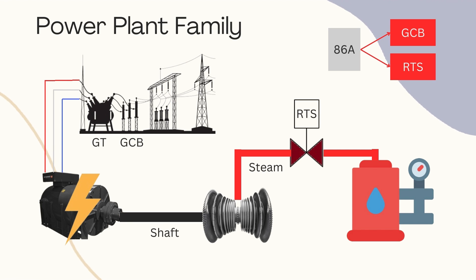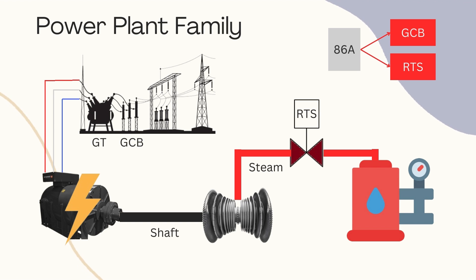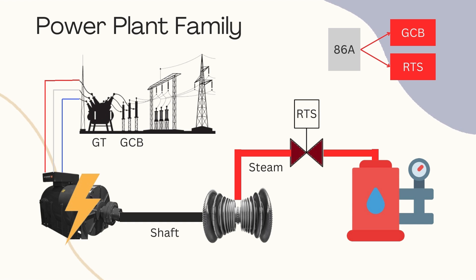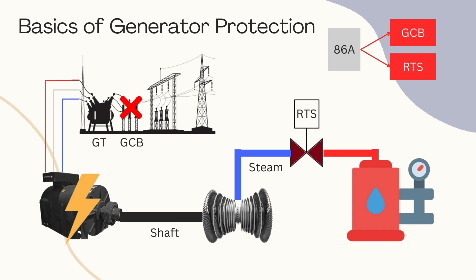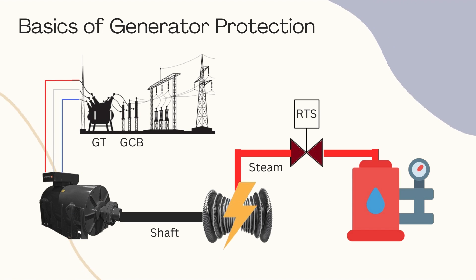If a fault occurs in the generator, the 86A relay will act, sending a trip command to the GCB and the Remote Trip Solenoid (RTS), through which steam passes from the boiler to the turbine. By isolating the generator from the grid and stopping the steam flow to the turbine, the rotor of the generator will slow down.